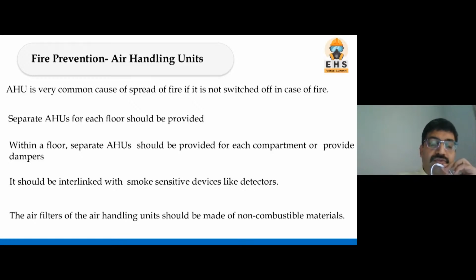Now within a floor also, a separate AHU should be provided for each compartment. Now see, suppose the floor is very high, a very long floor in terms of area. Then, as per the National Building Code, it is very clearly mentioned that there should be compartmentation of maximum, I'm sorry, minimum 750 square meters area. Means if the area is less than 750 square meters, that is okay. But if it is more than 750 square meters, then separate compartmentation should be provided. Then the damper should be provided so that it will be contained within that 750 square meter area only.